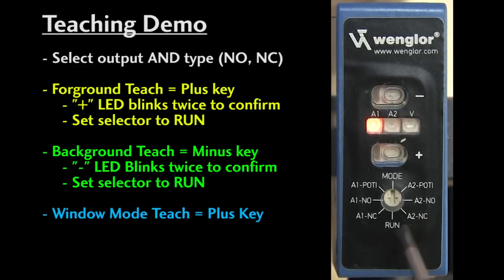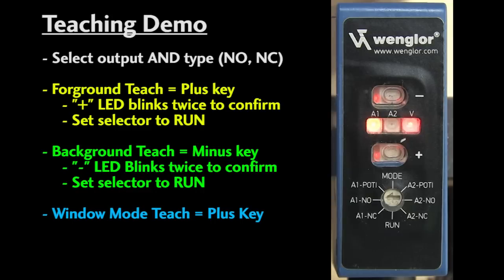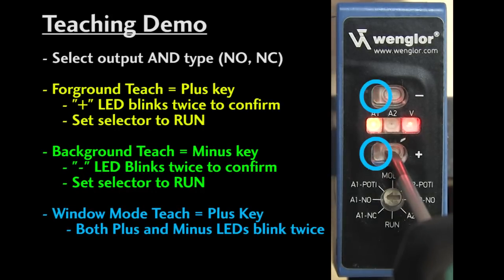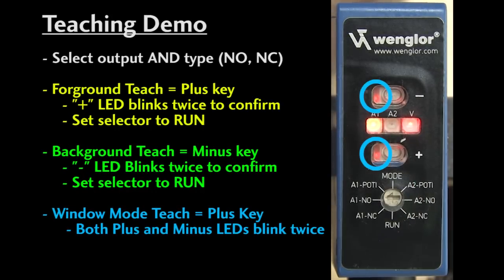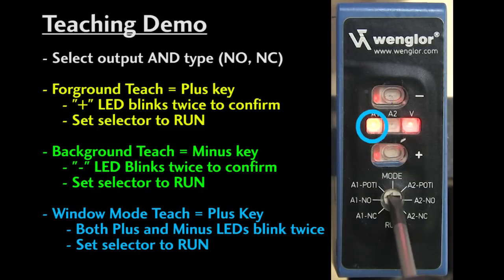We left output pin 1 in window mode. To teach that, set the object where you want the center of the window to be. Press the plus key. When both plus and minus LEDs blink twice – like this – window teach is done. Set the selector back to run. Now the sensor will only detect objects within a window around that midpoint.